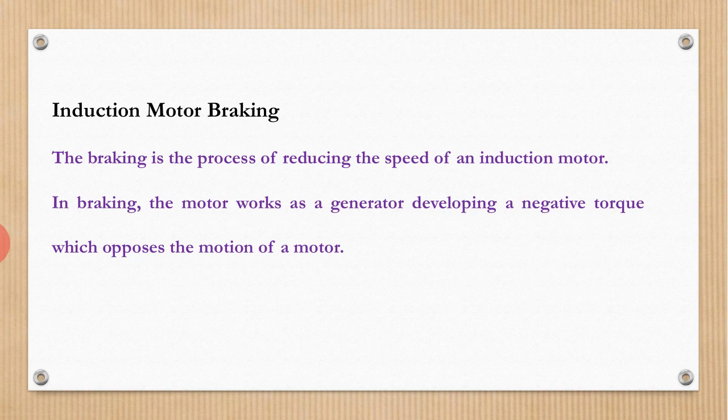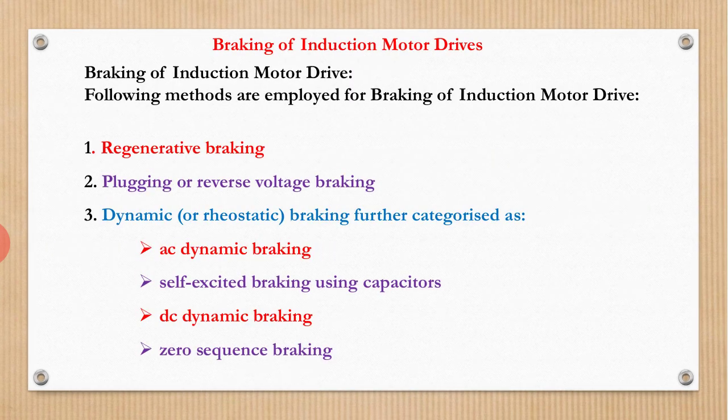I repeat here, during braking, it develops a negative torque which opposes the motion of the motor. Various methods are employed for braking of induction motor, namely regenerative braking, second one is plugging or reverse voltage braking, third one is dynamic or rheostatic braking, further categorized as AC dynamic braking, self-excited braking using capacitors, DC dynamic braking, zero sequence braking.